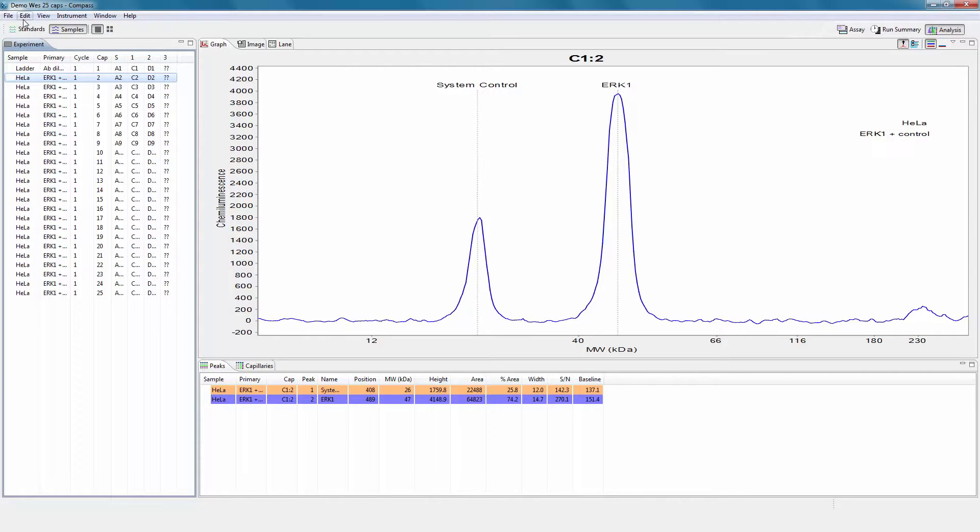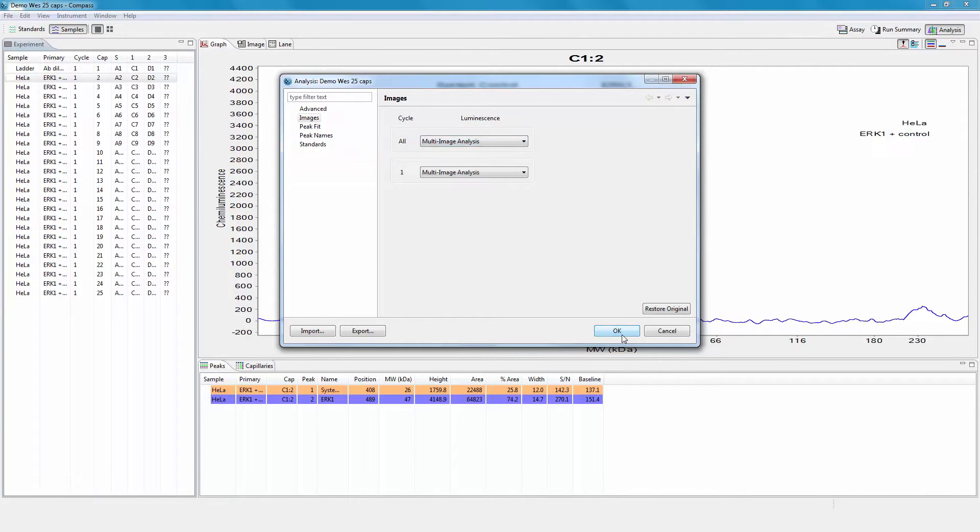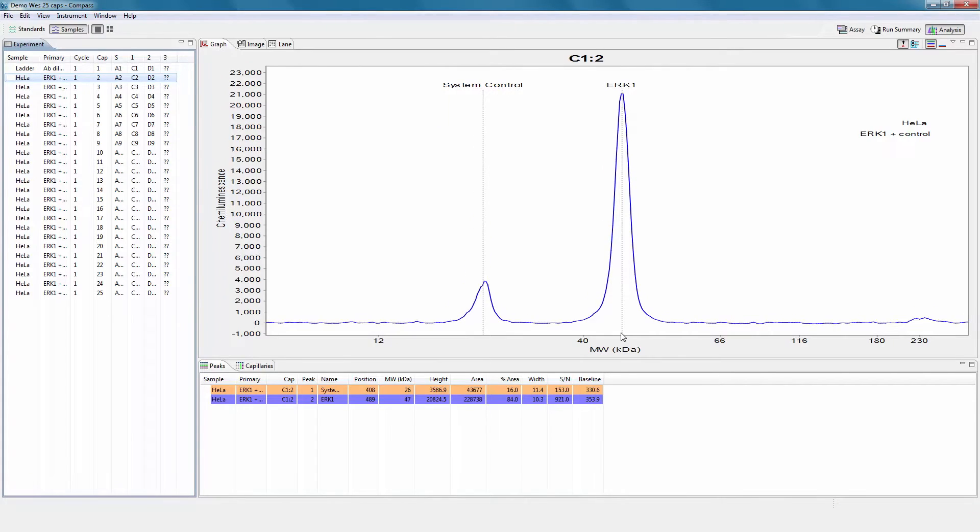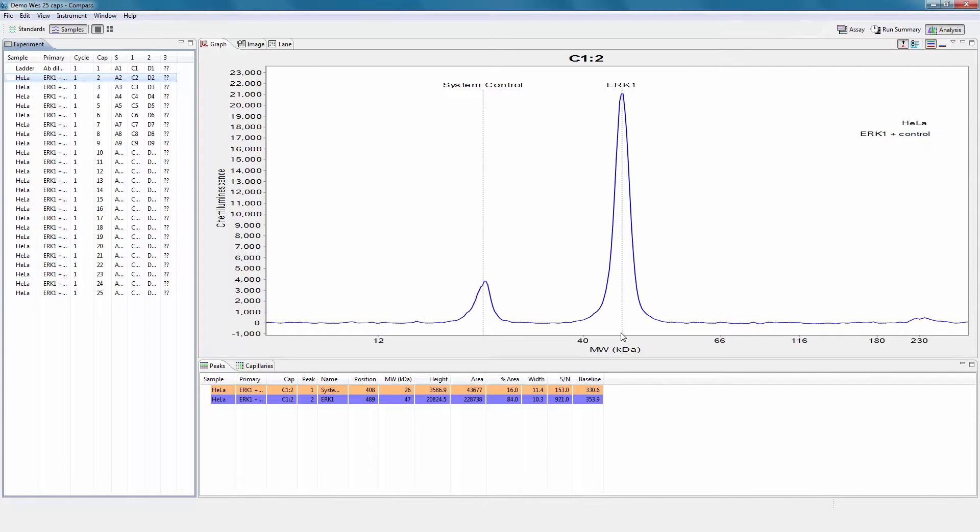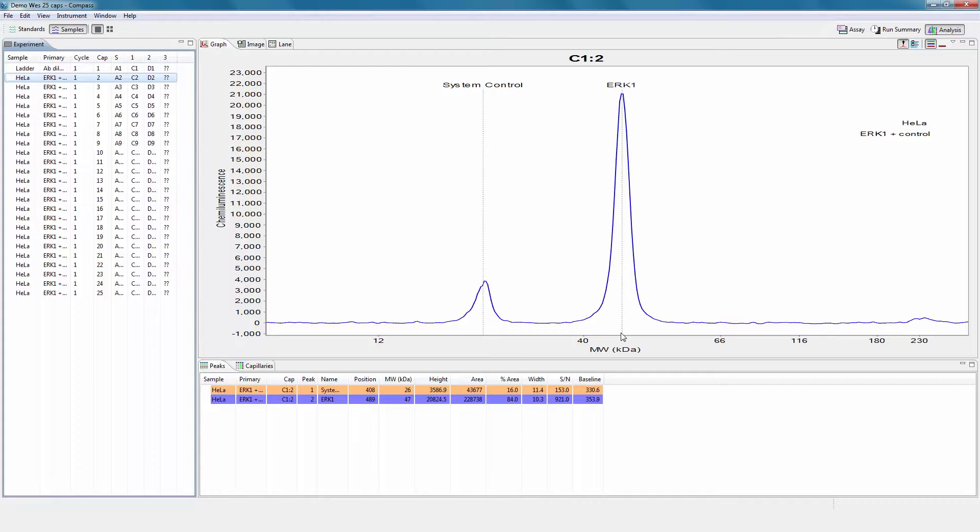In addition to the individual exposures, a multi-image analysis is included in the list. When selected, sample data displayed in the analysis screen is compiled from all exposures taken during the run, and utilized to calculate the chemiluminescence signal output at the time zero of the chemiluminescent reaction. This calculation represents the kinetics of chemiluminescent reaction, and helps to eliminate signal burnout that may occur with stronger signals and longer exposure times.